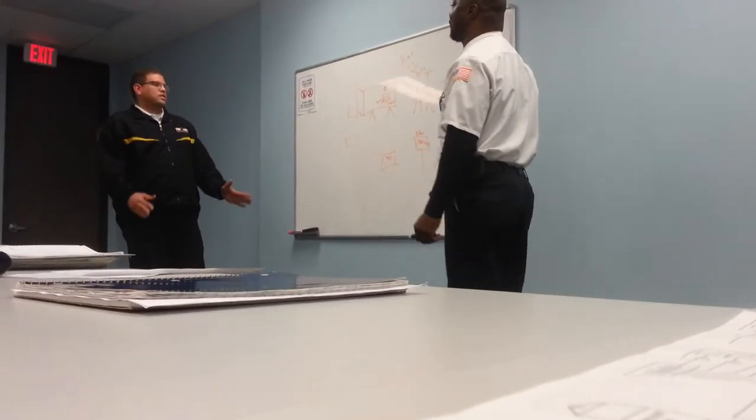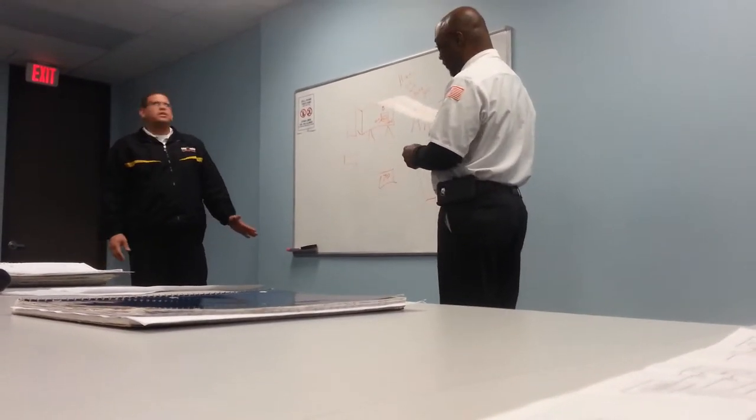A single-pole contactor. Yeah. So that one side was not closing all the way. So you only had 120. You didn't have 240.